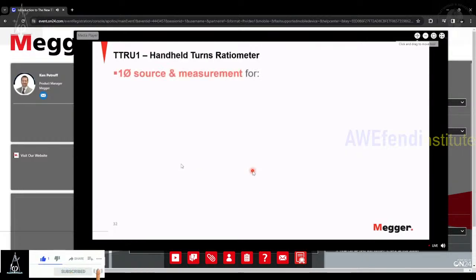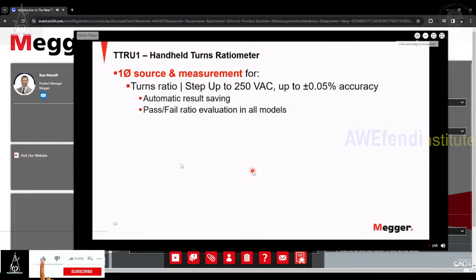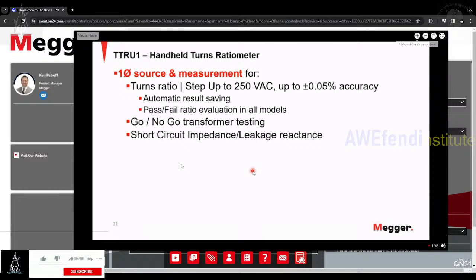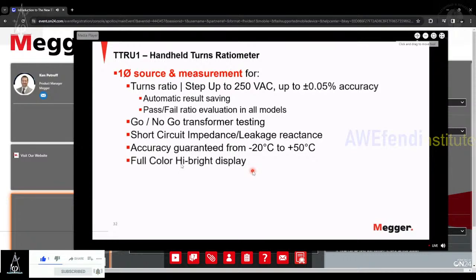So in summary, the TTRU1 is a single phase source and measurement device for turns ratio testing with automatic result saving and pass-fail ratio evaluation. In all the models, there is detailed go-no-go testing of a transformer, and an additional nameplate verification tool of the short circuit impedance and leakage reactance, guaranteed to work and provide reliable, repeatable results wherever you live in the world. We give you the full color high bright display to increase your confidence that you are testing the right transformer nameplate and following the connections to get the right results. And one of the last points is that we have AA rechargeable batteries, which will ensure that you are prepared to take on the day when you need to do your turns ratio testing.